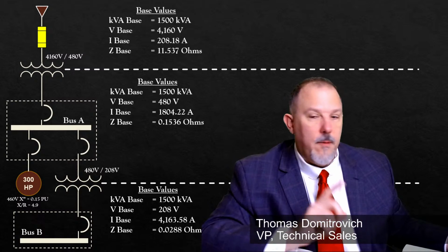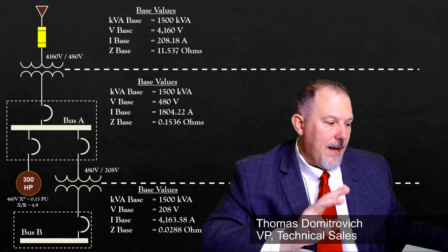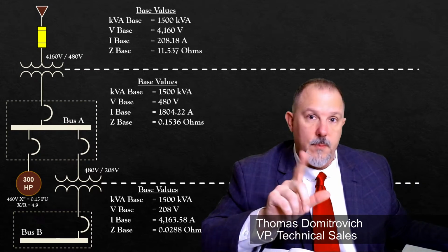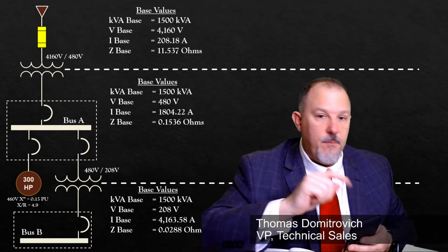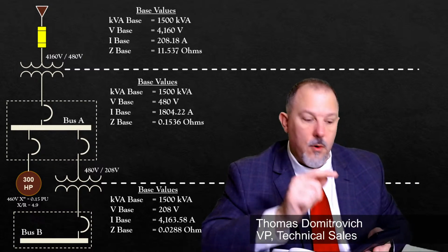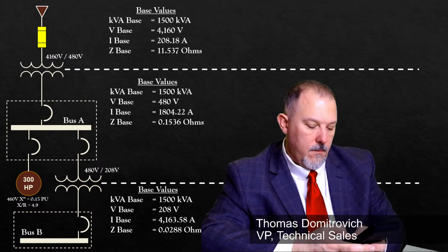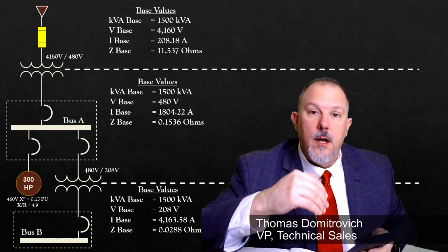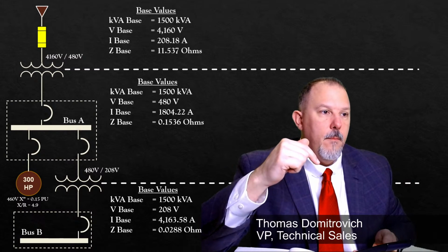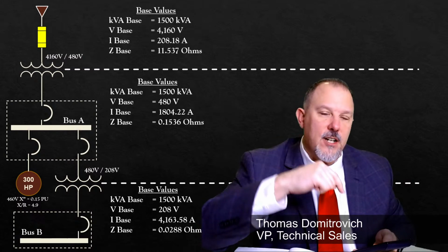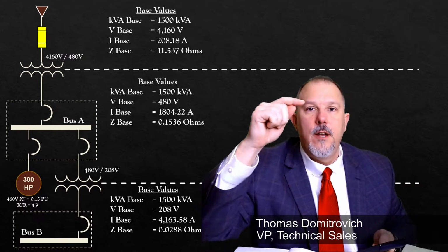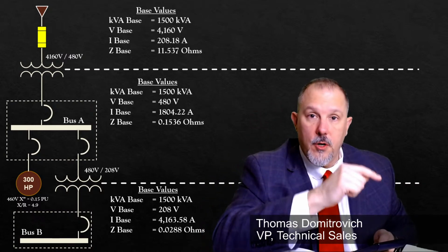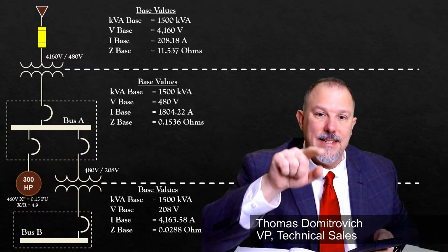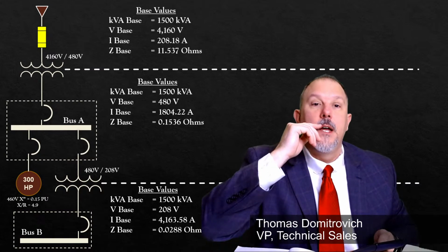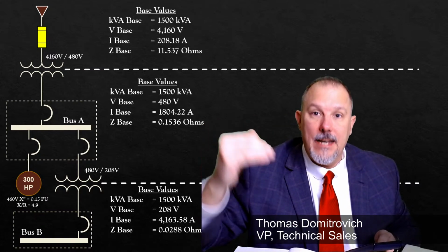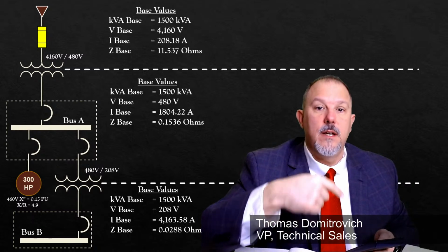Now, remember the ground fault current, zero sequence. We're going to add this 3 times. So we're going to have to do some multiplications here. But let's take this 5.5341 times 1804. Because remember, per unit is equal to actual over base. Actual equals per unit times the base. My base current is 1804 for bus A. So I have to multiply my per unit calculated ground fault current times 1804.